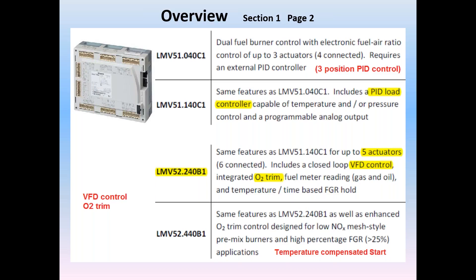Third is the most common application, the LMV52240. Again, all of the above features, but extends control now to five actuators, and includes variable frequency drive and oxygen trim, along with additional software features, such as time or temperature based FGR, flue gas recirculation.